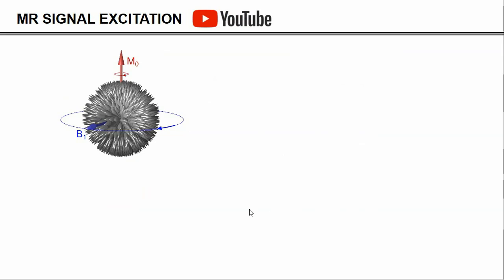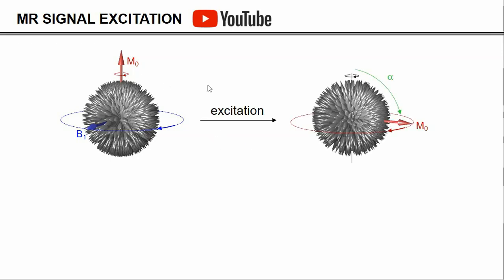So how do we achieve excitation in NMR? Well, from an earlier video, you may recall that the magnetization that we're trying to detect is along the z-axis, and it is the sum of many, many nuclear spins that are all rotating at the Larmor frequency. In order to rotate the magnetization to the xy plane, we need a secondary magnetic field B1 that rotates also at the Larmor frequency, and is perpendicular to the magnetization. If that is true, then the magnetization experiences a rotational force, or a torque, and when the rotation angle alpha is adjusted to be 90 degrees, we're getting full excitation of our magnetization.